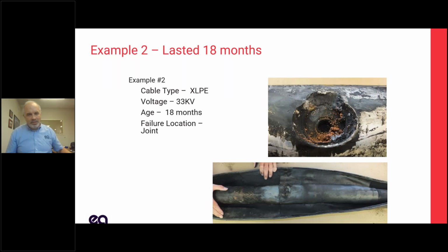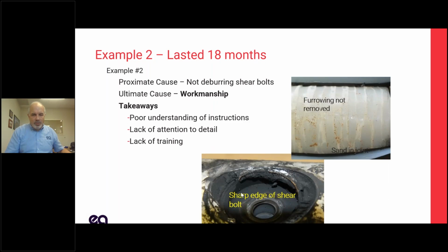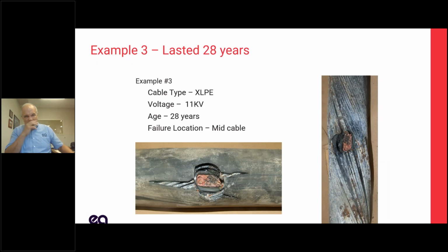Here's a second one. This one lasted 18 months. Okay, it's still in our infant mortality. And what happened is the 33 kV cable, the shear bolt edge was not filed down, cut through the various insulation layers, caused a failure. But you can see the insulation trimming, where the semicon was removed, that was done poorly. This could have failed for a variety of reasons. So again, workmanship.